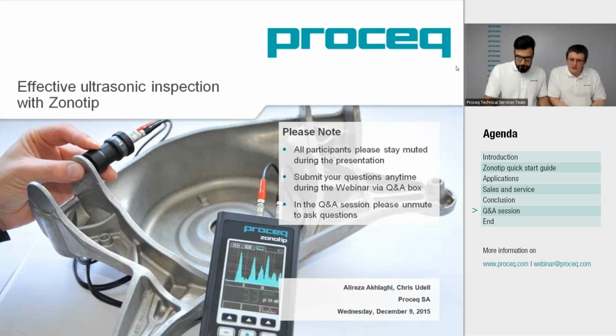There's another one there. How often do you calibrate? That's quite a good question. Usually in standards, you say you do it at the start and end. Every time, definitely at the start and the end of every shift. So you make sure that throughout your inspection, your results have been consistent. Now, if anything changes in between the start and end of the shift, then you have to recalibrate. If you disconnect the probe, for example, or if the temperature is changing, or anything like that, it's best to recalibrate.